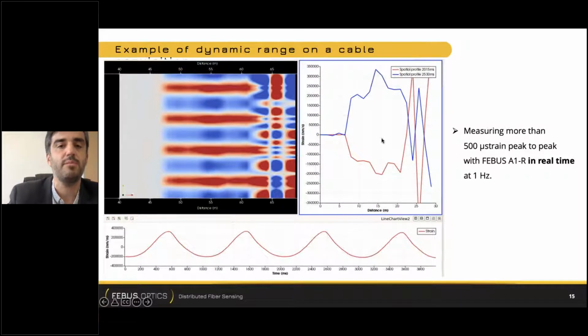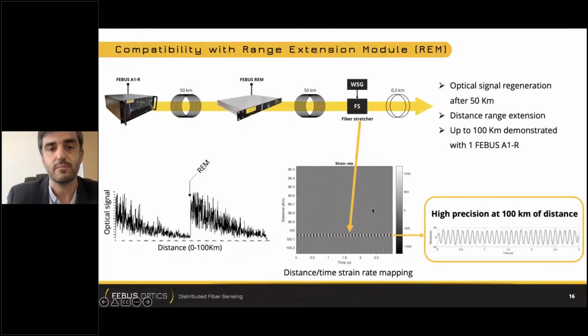And here you can see peak to peak, we are at 500 microstrain at 1 Hertz. If you remember, we were at something like 3 picostrain at this frequency. So it means something like between 7 and 8 orders of magnitude between what we measure and what we are able to measure. So this is the proof of a high dynamic range.